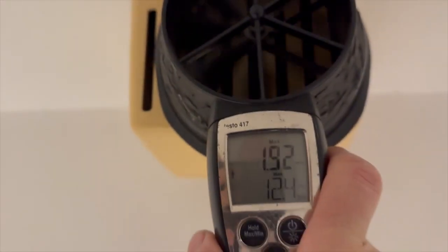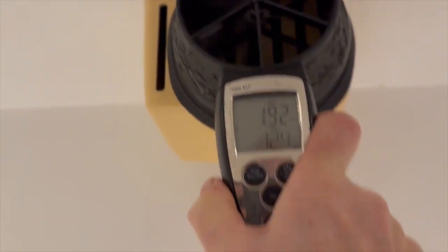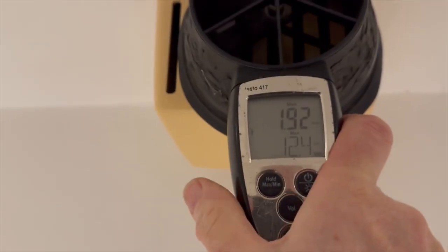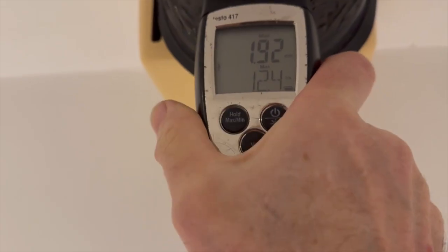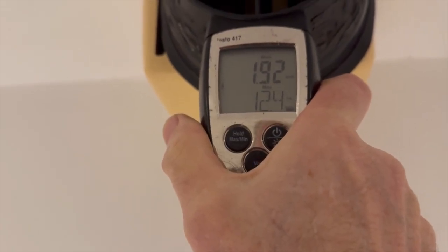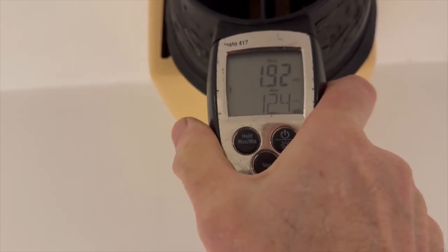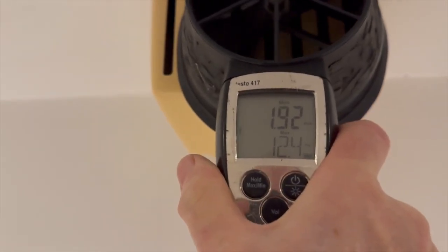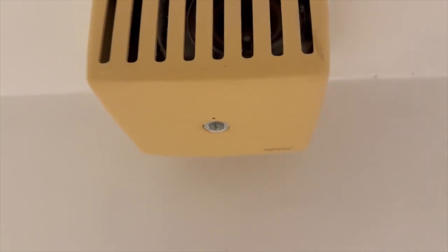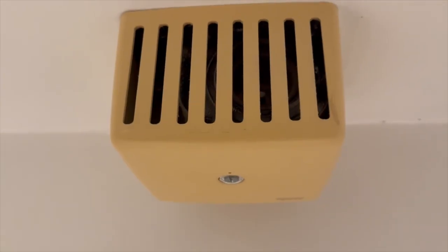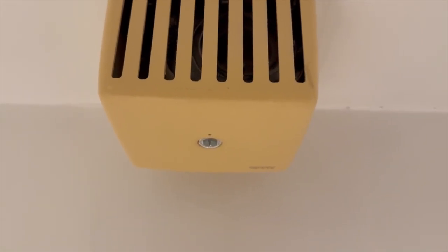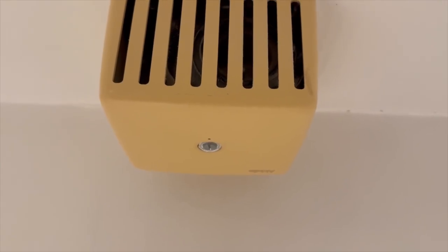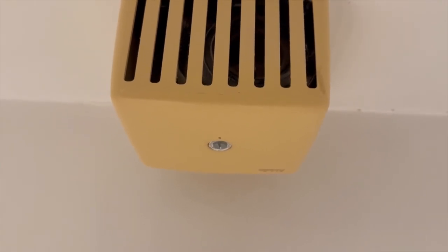Using two hands, I was able to get it up to 12.4. 15 litres a second is what you aim for, but most people are well below that, so it's not bad and I wouldn't worry too much about it. But make sure to keep the extractor fan running for half an hour and the door closed, because you don't want the vapour coming from the bathroom to the rest of the property.